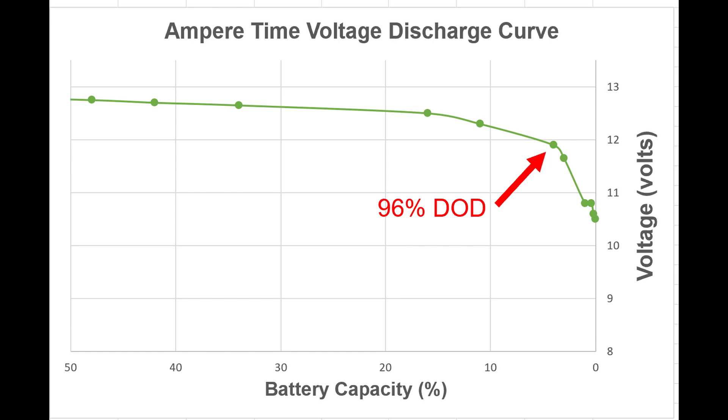Here is the voltage discharge curve for the Ampere Time 100 amp hour battery. It starts at 12.8 volts, typical of lithium iron phosphate, and the discharge curve is rather shallow — the voltage doesn't drop quickly like it does on a lead acid battery, making it difficult to tell remaining capacity simply by measuring voltage. But as you approach 100% depth of discharge, the curve drops rapidly. This battery drops below 12.0 volts at 96% depth of discharge, meaning you can get almost 100% of capacity at 12 volts and above.